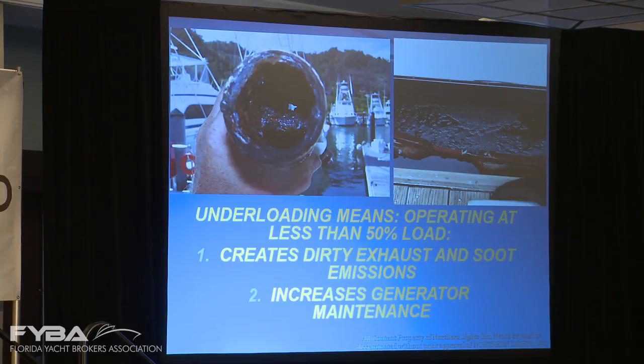Perhaps the biggest thing to talk about with generators, the most important part, concerns the loading of the generator. So we have a big problem with loading, and I can't really emphasize this enough. I can't even begin to tell you how many problems it causes. I'd say for every 1,000 phone calls or emails that we get that have any kind of a problem at all, we might get one that involves not being able to carry the load, and 999 that are directly related to not enough load. So problems related directly to low load. Underloading means less than 50% load.